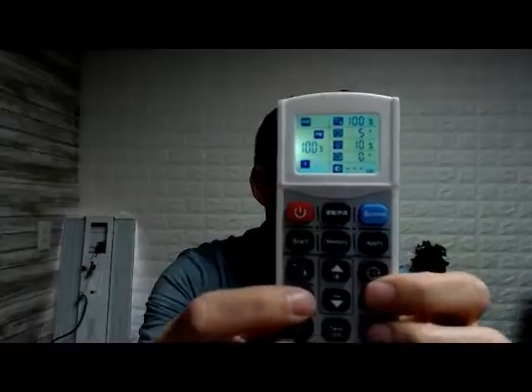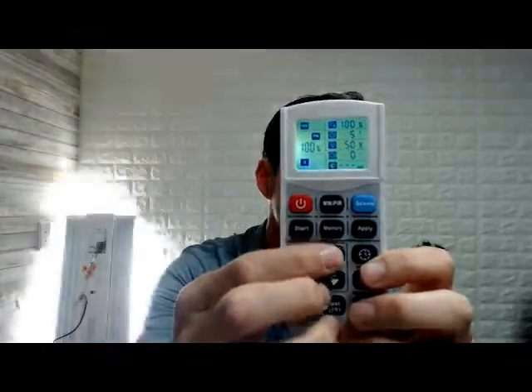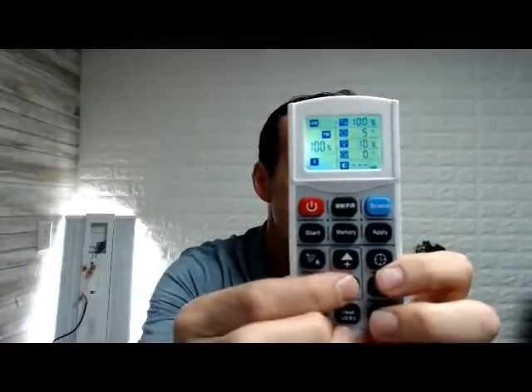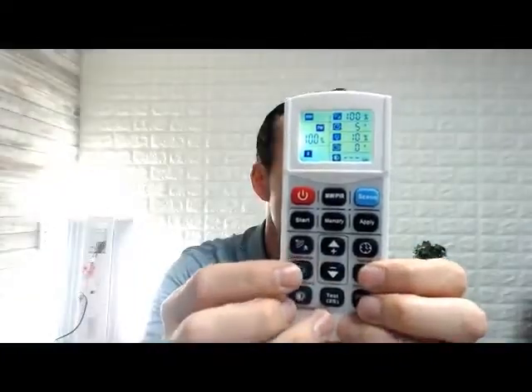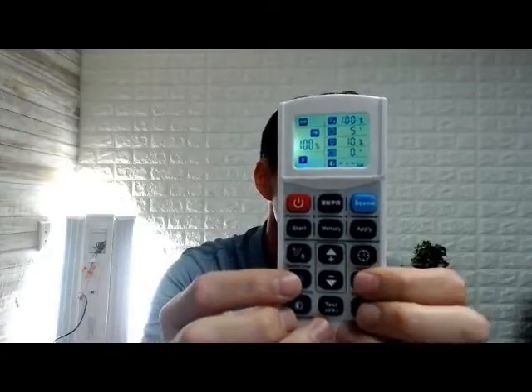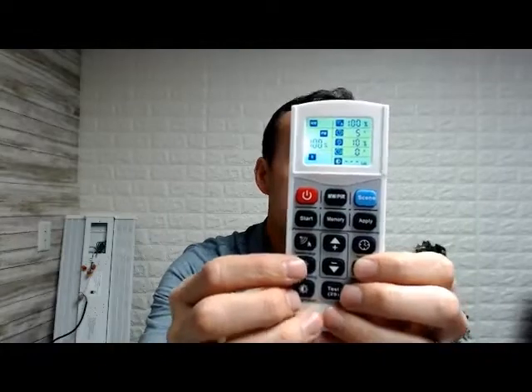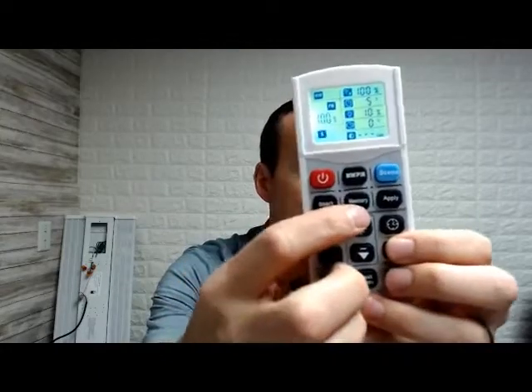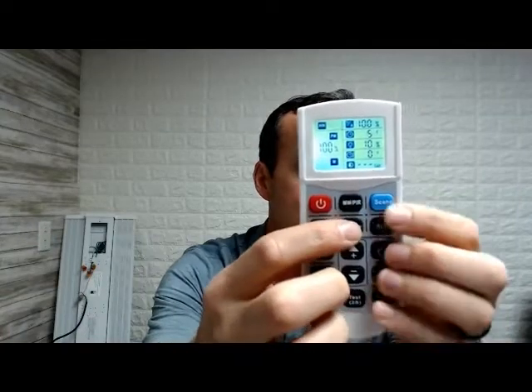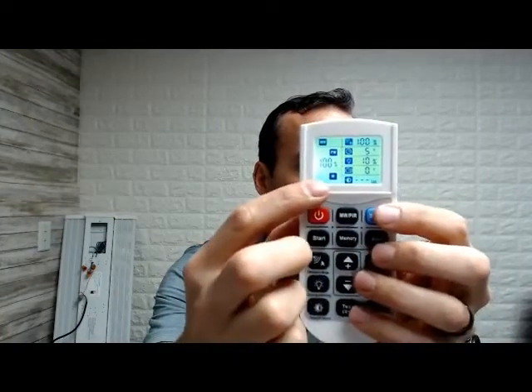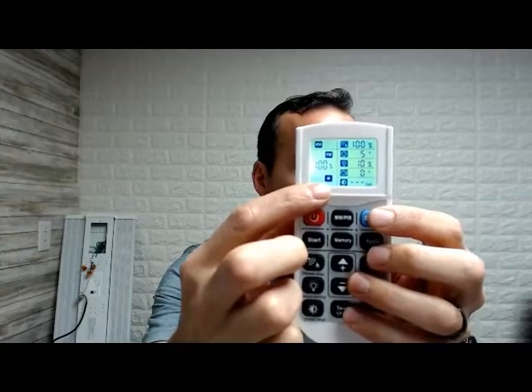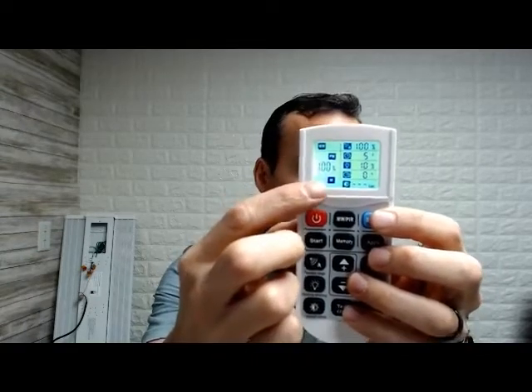Next piece we're going to go down to is our dim level. Once I after those five seconds, what am I going to dim down to? And then how long will I be at that dim level? So right now, I'm going to set it to 10%. And then the last piece here is the standby time. Right now, I'm going to leave the standby time at zero just so I can use this for an example. Now here in the middle, once I have all those settings set, here in the middle is memory. I'm going to press the M for memory, and you can see that I'm no longer blinking up here. But now I'm set to M for the memory. All right, 100%, 5, 10, and zero.